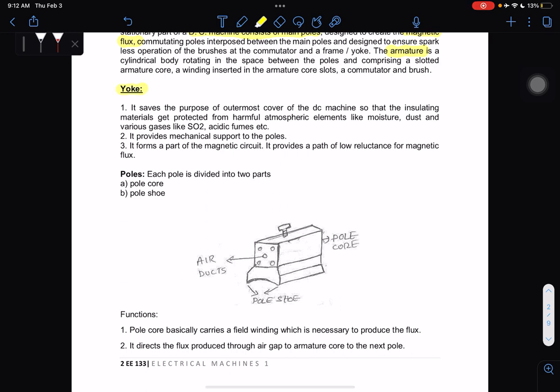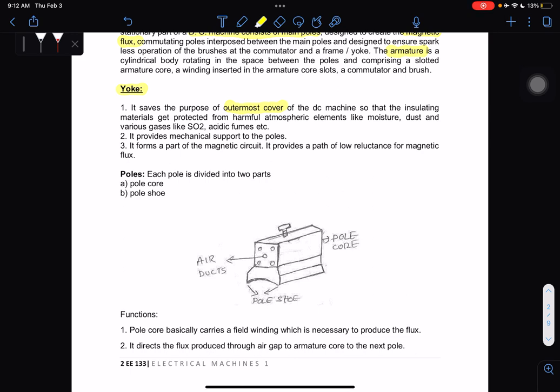First, we have the yoke. The yoke serves the purpose of the outermost cover of the DC machine. It provides mechanical support to the poles. And it forms a part of the magnetic circuit — it provides a path of low reluctance for magnetic flux.